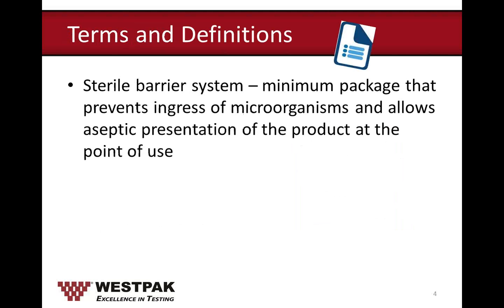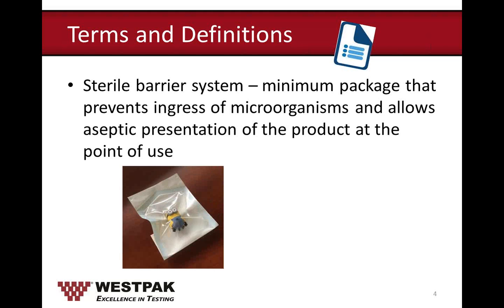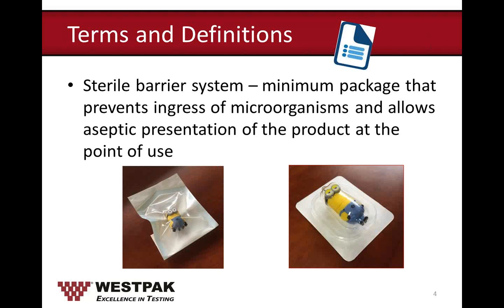Let's go over the basic terms and definitions. The sterile barrier system, or SBS, is a minimum package that prevents ingress of microorganisms and allows aseptic presentation of the product at the point of use. For example, here's Minion Dave placed in a plastic film Tyvek pouch. And here's Minion Tim in a thermoform tray with a Tyvek lid. These Minions are my star role models for many presentations because a lot of the products we test at Westpak are confidential — so pictures are worth a thousand words.